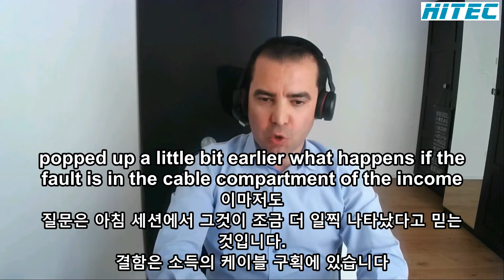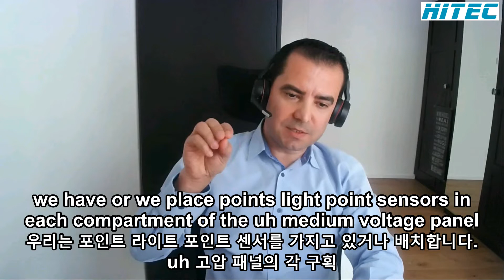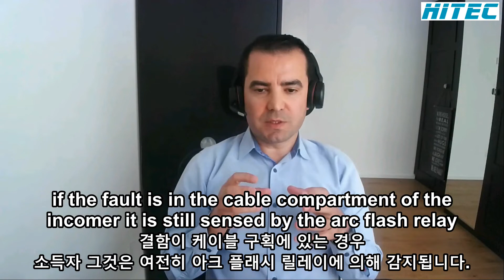Even this question was, I believe, in the morning session. It popped up a little bit earlier. What happens if the fault is in the cable compartment of the incomer? At the end of the day, like previously explained by Kerem, we place light point sensors in each compartment of the medium voltage panel. If the fault is in the cable compartment of the incomer, it is still sensed by the arc flash relay. Here, the CB tripping signal is sent both to the incomer and also to the upstream circuit breaker, which is feeding our system. Therefore, it also helps getting rid of the fault.